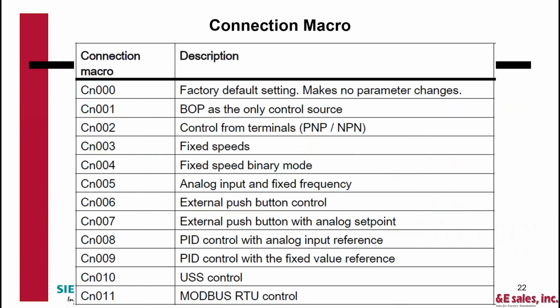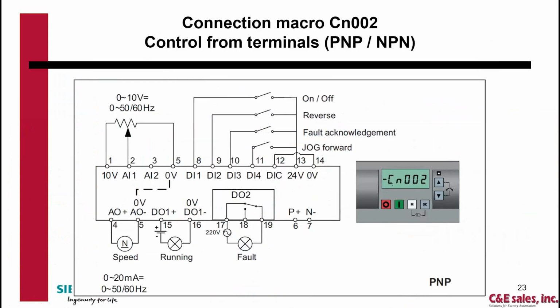So connection macro, here's basically the 11 that are available. For our example, we're going to use Cn002 because I have a speed potentiometer for speed reference and then a start signal to the drive. From Cn002, here's where it's expecting the terminals to be pre-configured from the macro. You see your analog in. It shows a speed pot between 1, 2, and 3, or 1, 2, and 5. You've got a digital input for on-off. Digital input 1 is on-off, 2 is reverse, 3 is fault acknowledge, 4 would be a jog.